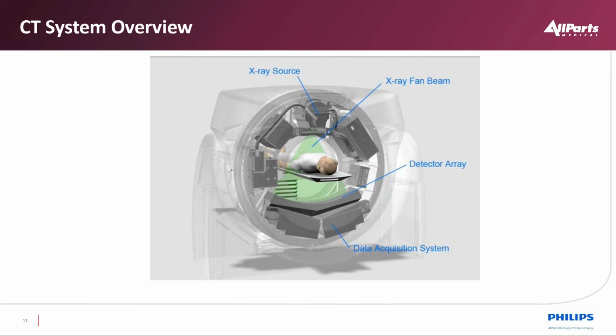So as you can see, we have that green projected to the detector. That detector then converts that X-ray energy into visible light through a process using a crystal. That crystal then has a photodiode behind it, which turns it into analog data that we then digitize. So we have quite a number of channels, and then we add rows to this as well. With the rows, we collect all this data through the data acquisition subsystem and transmit it to our recon computer that will then assemble all that data on the hard drives as a cylinder of raw data. And then we'll process out of that raw data a completed image that you get to see on the screen that would be called a slice, okay?